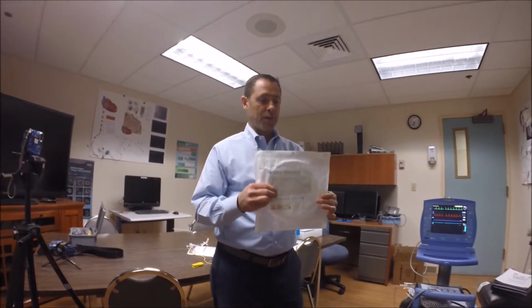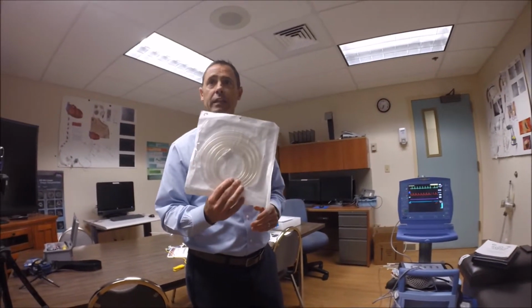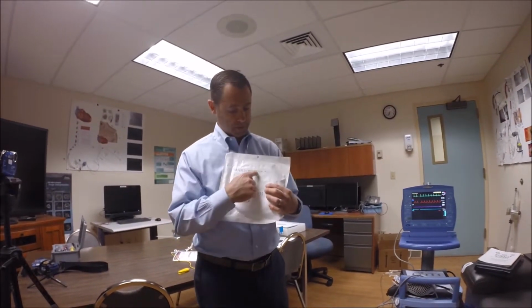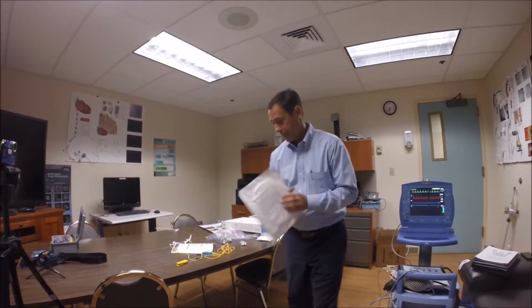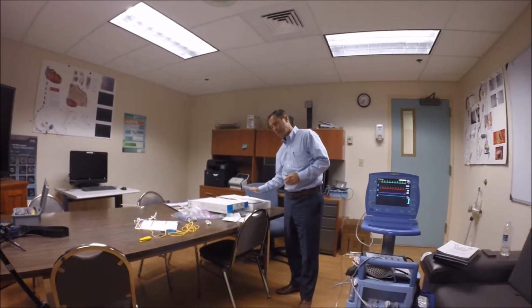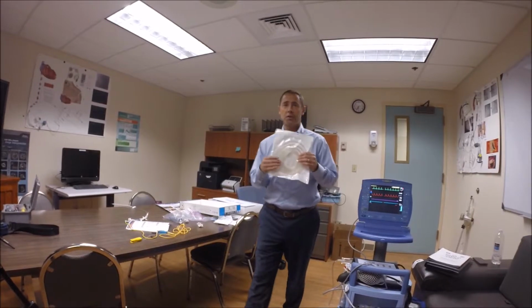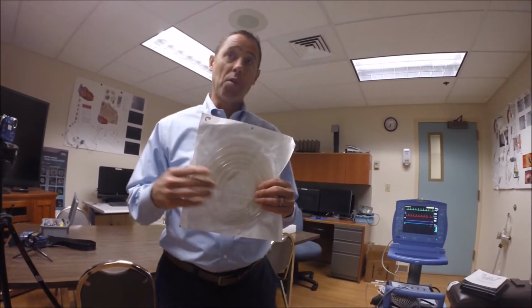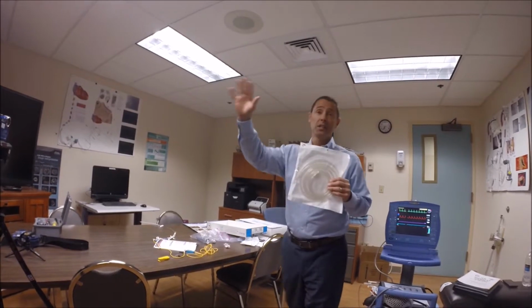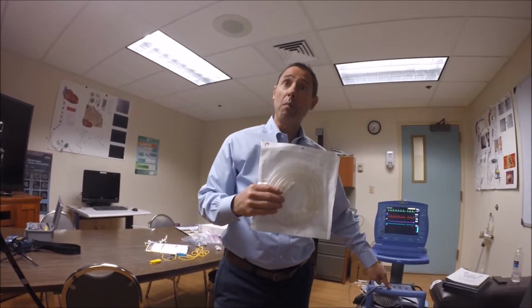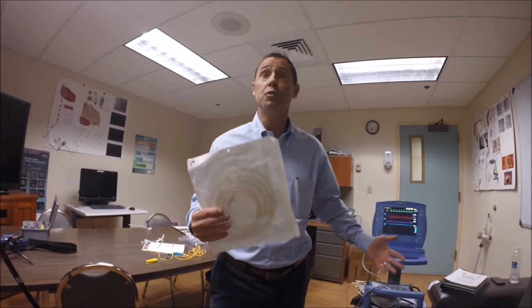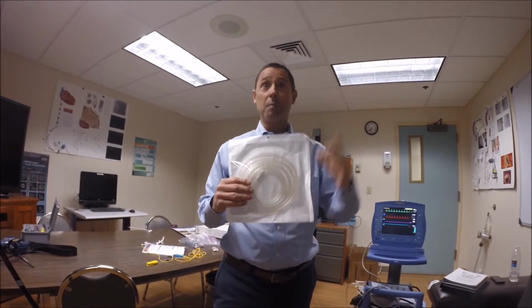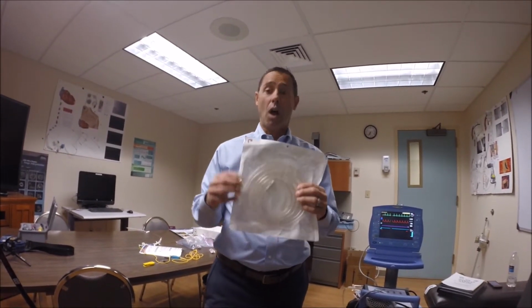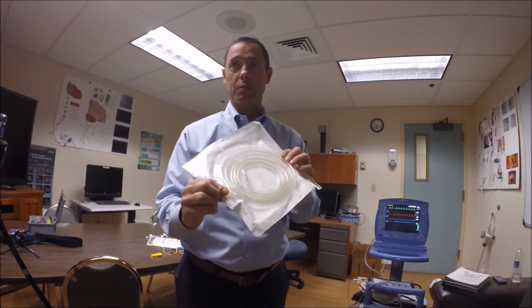Okay. So inside of every catheter box, you'll find this helium adapter tubing. You'll notice it says Datascope. We, Arrow, include one on top in every single catheter box. This goes with transport if you're transporting with an Arrow catheter to a facility that does not use an Arrow pump. If you're transporting out of here, which you guys don't, because everyone here uses Arrow. However, this can also be used for your pump that's upstairs, your CS300, with an Arrow catheter on that pump. Excellent. So there's your adapter tubing, and there's your adapter right there.